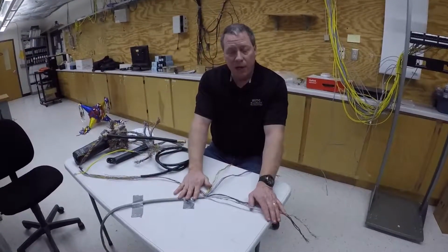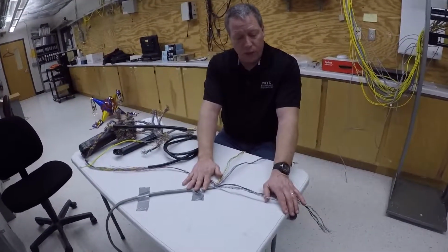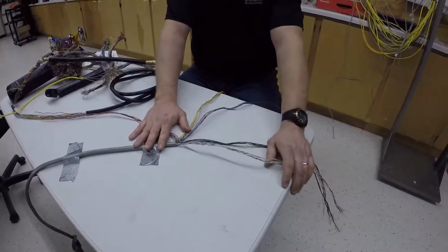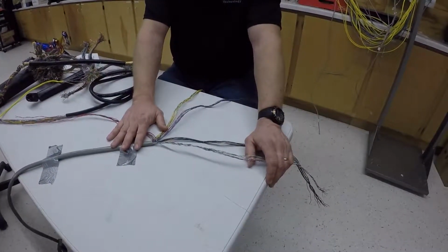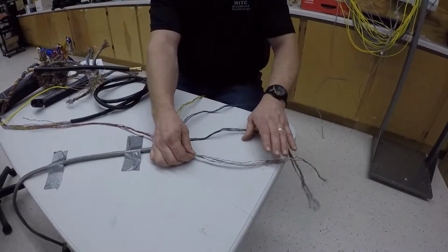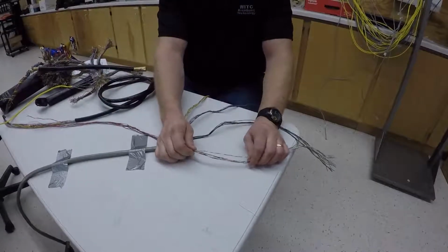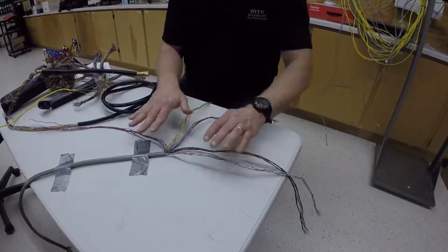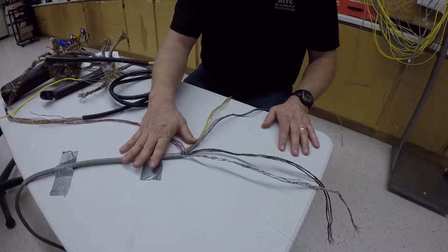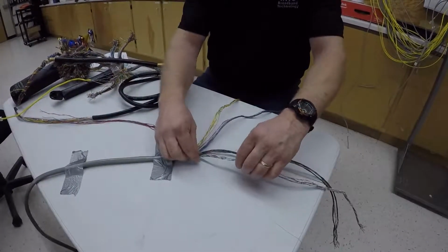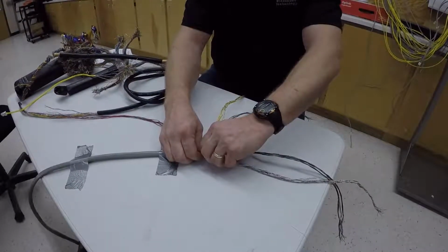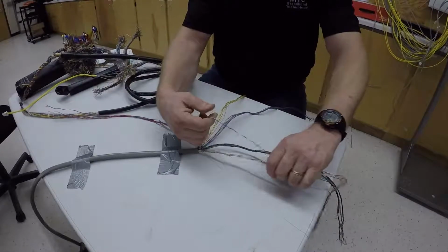The cable I have here is a Cat 3 cable for voice only, and you'd find this in an environment inside a building, which you would communicate or have networks for voice conversations only. And what we have here is a 25 pair cable, 24 gauge, and I have them separated in pairs of 5. So I'm going to go through these 5 and go through the color codes.